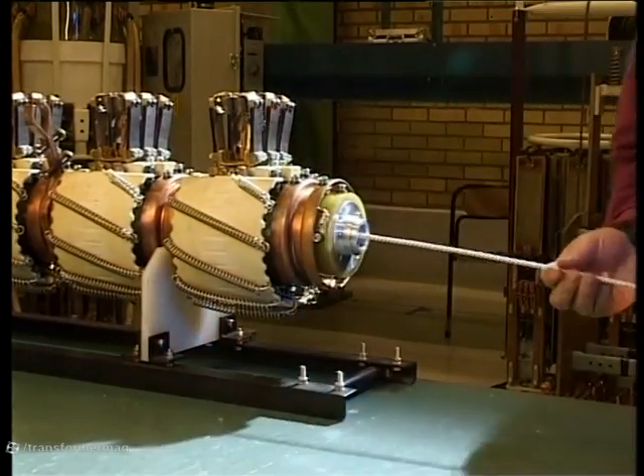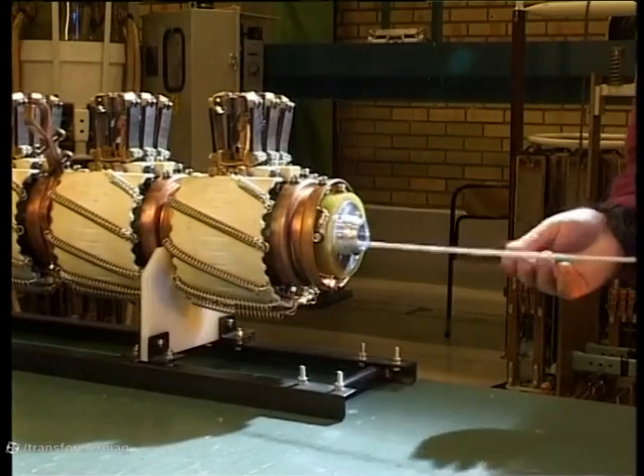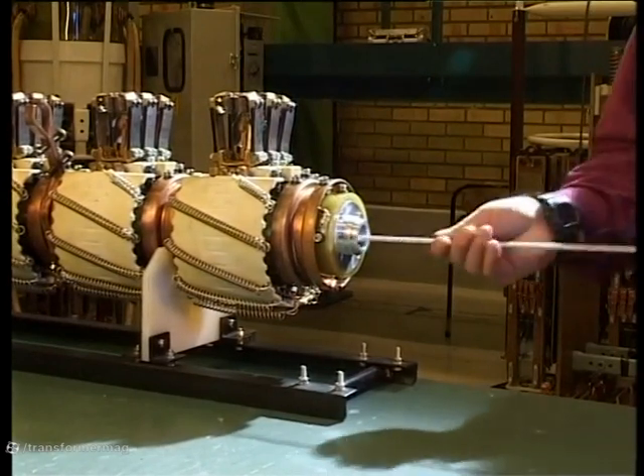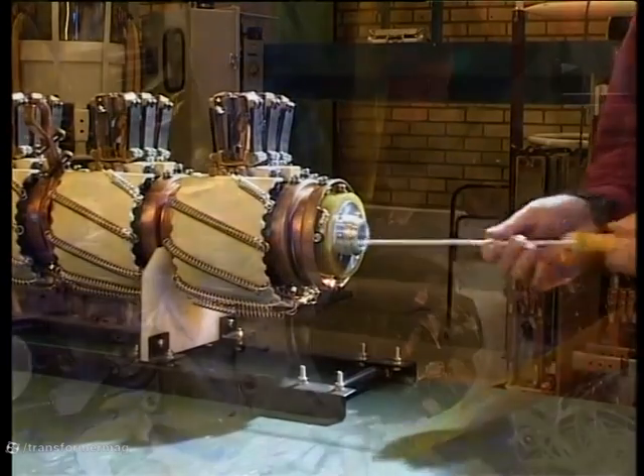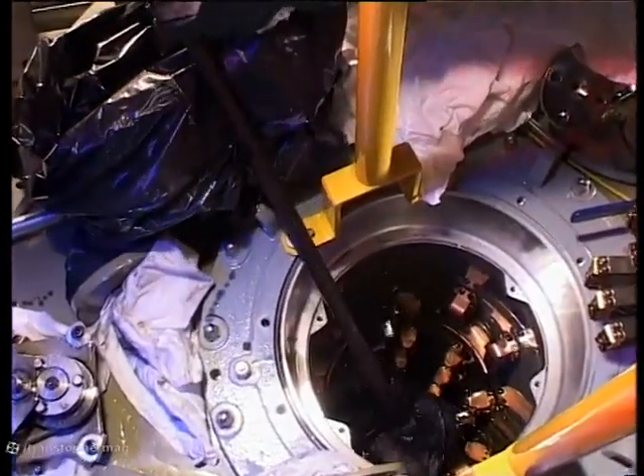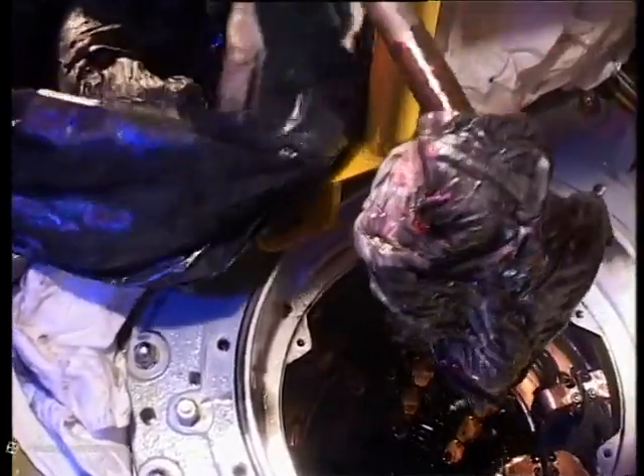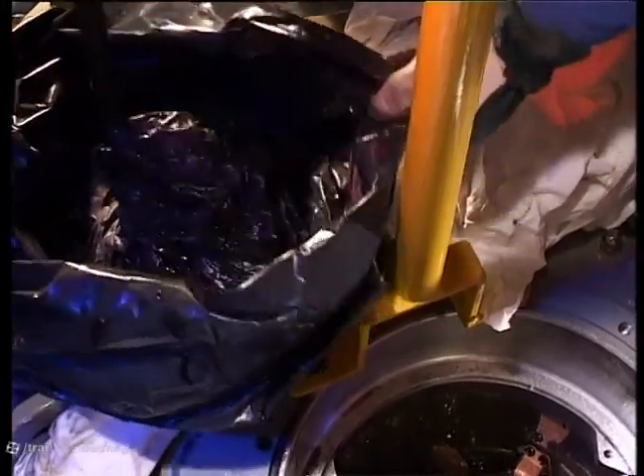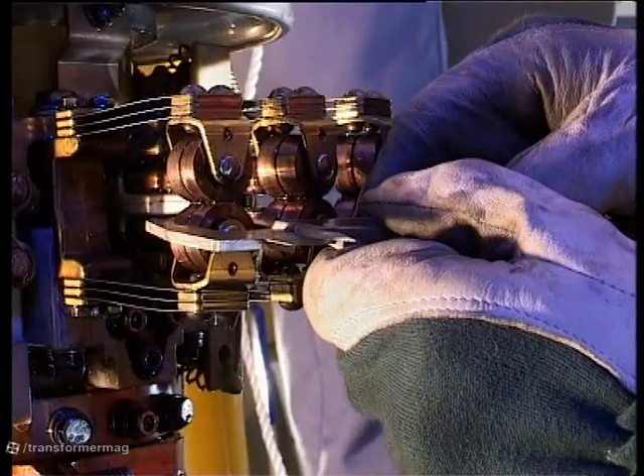Clean the inside of the selector switch shaft with a brush. Move the brush up and down, turning it at the same time. Flush out the cylinder using a brush if necessary. Use lint-free cloths to collect up any remaining oil. For measurement of moving and fixed contacts, see the maintenance guide where the dimensions are given and the method is described.